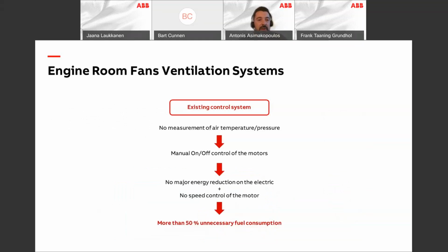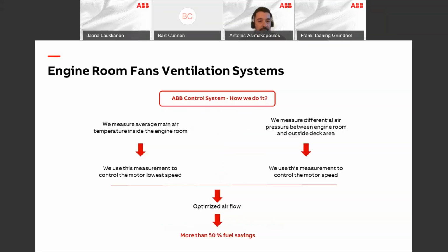So let's see how the engine room fan ventilation systems are today, more or less. There's no measurement of air temperature or differential pressure. Usually we have manual on-off control of the motors. So as I said before, there is no major energy reduction on the electric motor, and we don't have any speed control of the motor. This means that we may have more than 50% unnecessary fuel consumption for the operation of the fans.